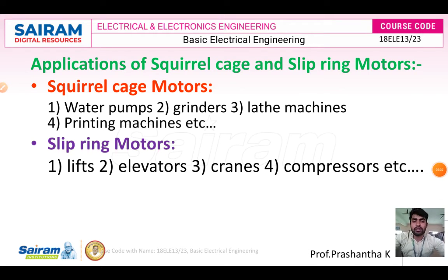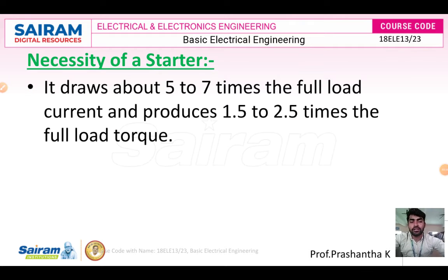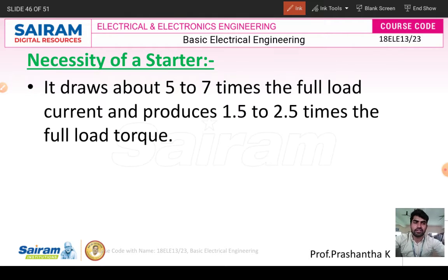Let's see how to start the 3 phase induction motor. For a single phase induction motor, we want a capacitor for starting. But for a 3 phase induction motor, we want some starters, right? According to the DC generator concept also, if the conductors in the rotor are not rotating, the back EMF will not be there. So whatever supply voltage we give is converted into current, because the rotor resistance of the armature in the induction motor is very low, like 0 to 1 ohm.